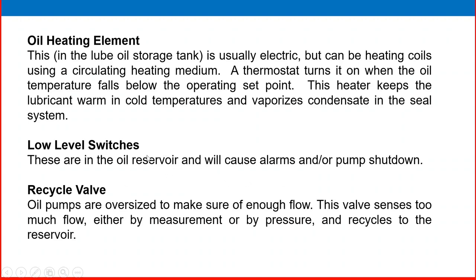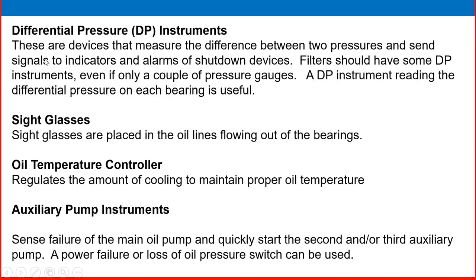A recycle valve is provided since oil pumps are oversized to ensure sufficient flow — this valve senses excess flow by measurement, pressure, or recycles back to the reservoir. Differential pressure instruments measure the difference between two pressures and send signals to indicators, alarms, or shutdown devices. Filters should have DP instruments, and measuring differential pressure across each bearing is useful. Sight glasses are also used.